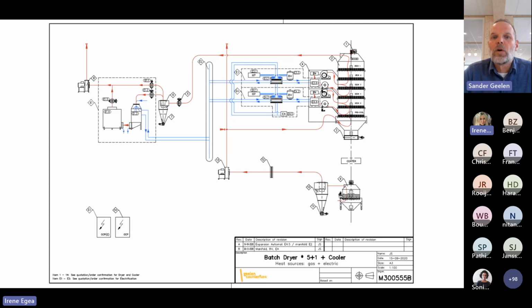The blue lines are water, but I will go into that in a second. But the red lines: you first see one top red line going out on the top left corner being exhausted, and that's the way we used to do it before. And then at the bottom you see that the cooler red line is coming back into the dryer. And we've been doing that for a long time, reusing the cooling air, which contains a lot of energy, of course, and reusing that up in the dryer.